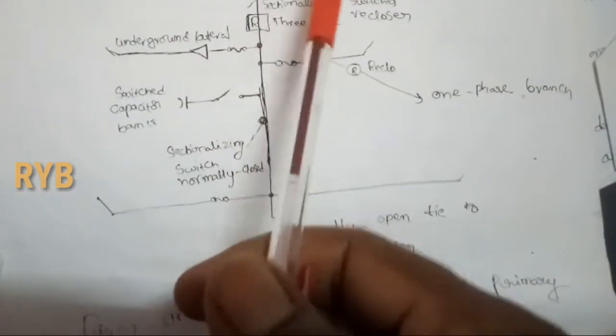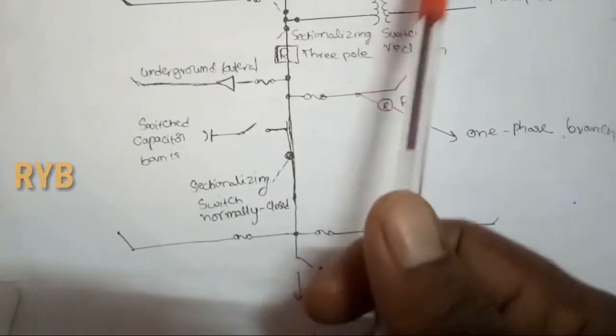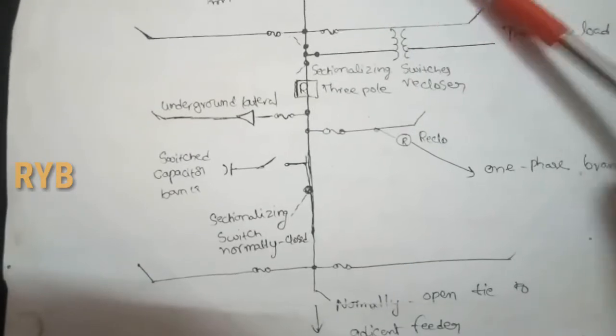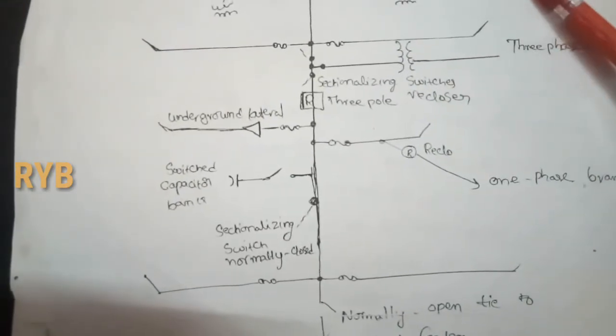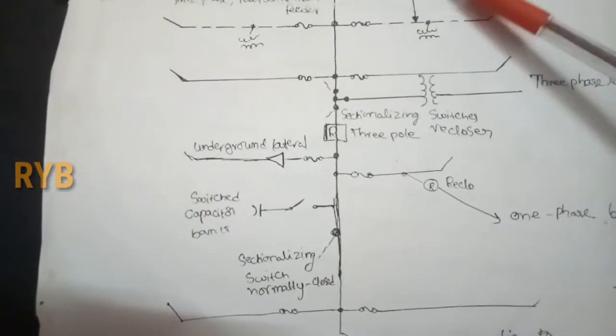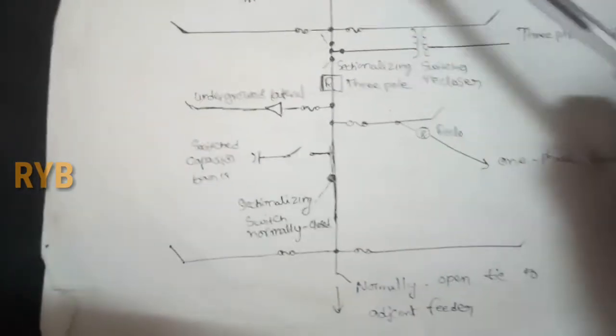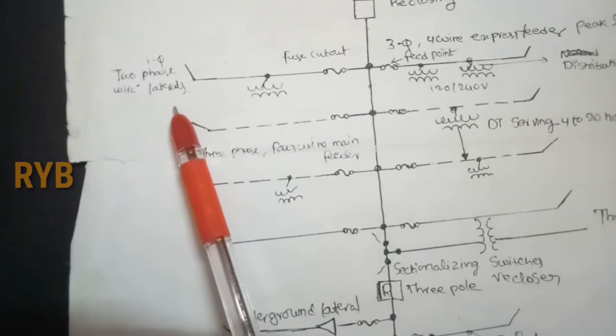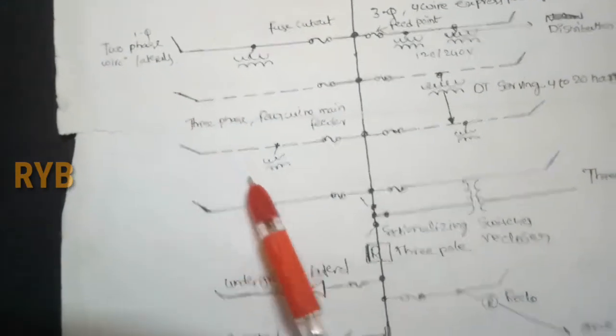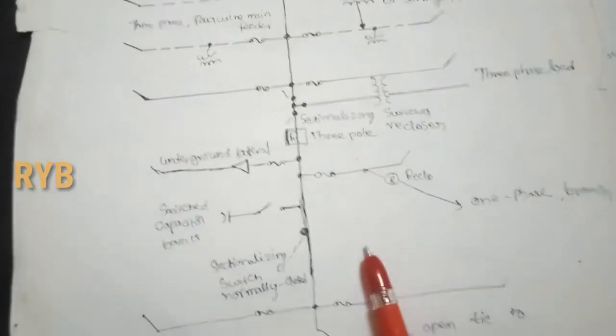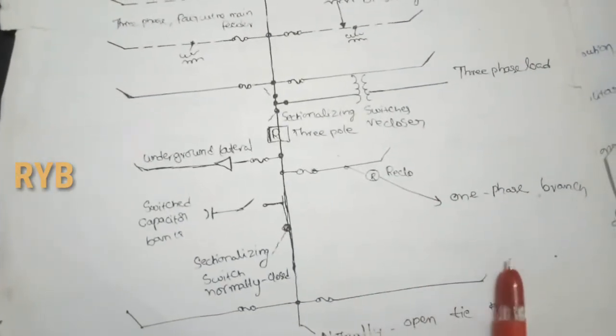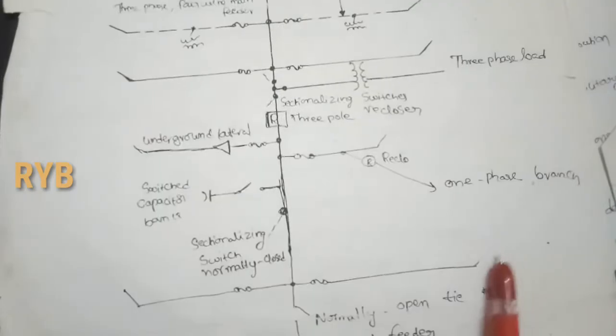This is the single line diagram of the primary distribution feeder. It shows distribution transformers each servicing approximately 4 to 20 houses. The diagram includes a three-phase four-wire express feeder, single-phase two-wire laterals, and sectionalizing switches. Sublaterals are also allowed but are not shown in this particular diagram.